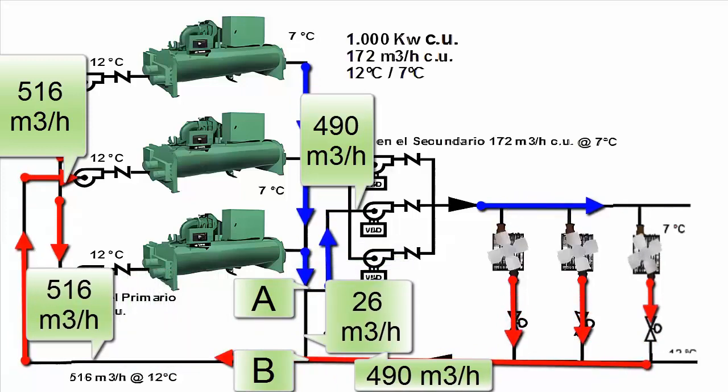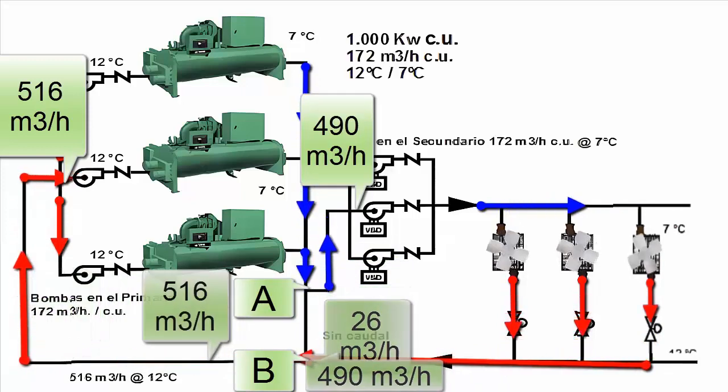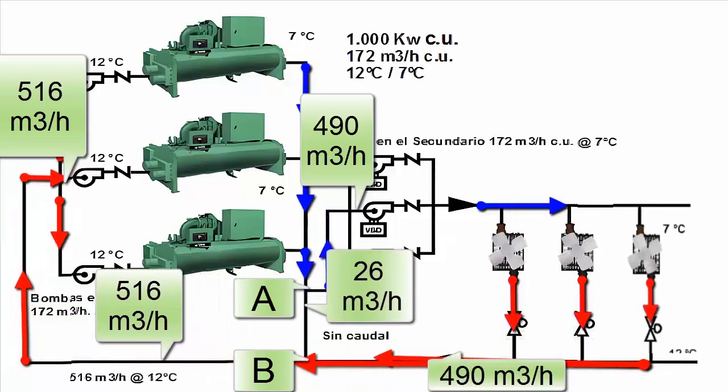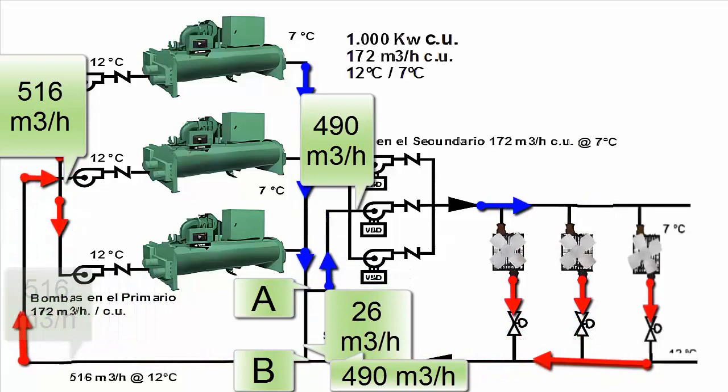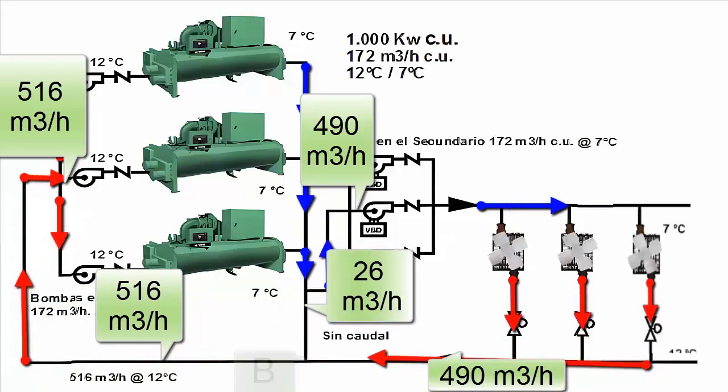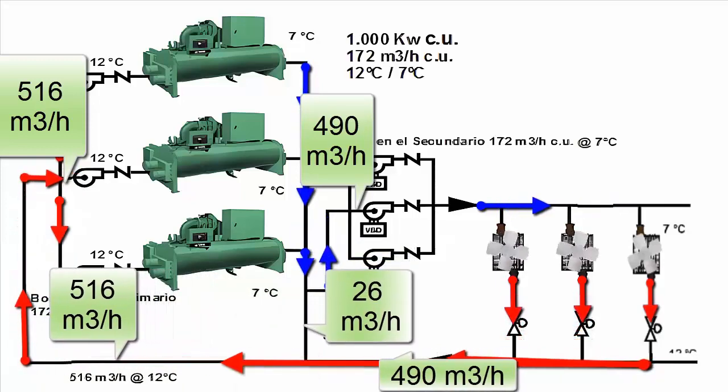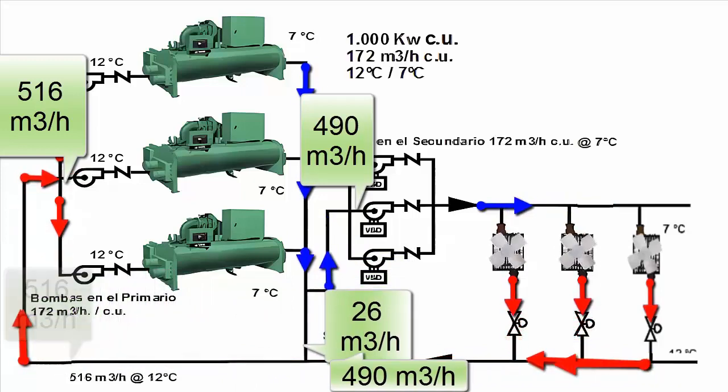In this scenario, since the three water chillers are still running and always handle the same flow, there is excess chilled water that can still be used. Therefore, it is directed through this bypass to contribute to cooling the water returning from the building.